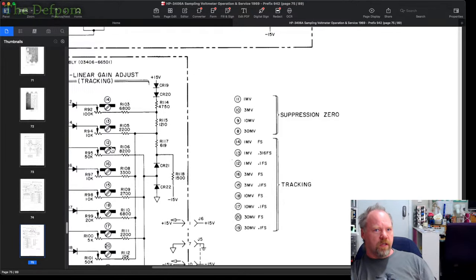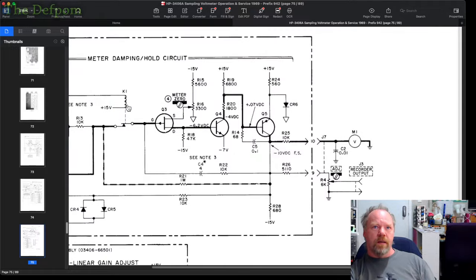I've done mechanical stuff like the switches, because before I cleaned the switches, it was behaving better. But it wouldn't get a full-scale reading. It was only getting like halfway up. And it's a bit erratic, so I cleaned the switches with some DeoxIT, sprayed that in there because they're all open. And that fixed that problem, and then it's reading way up. So maybe it's reading low, and someone's been in there twiddling pots before I got it, and they tried to adjust it, and it's messed it up. I don't know.